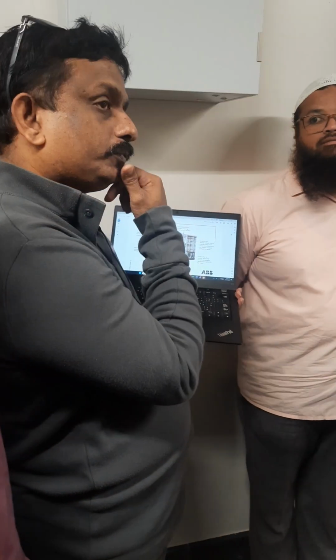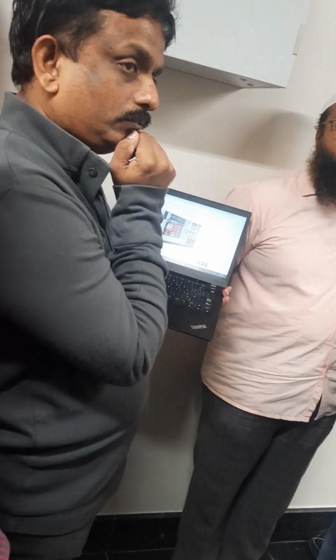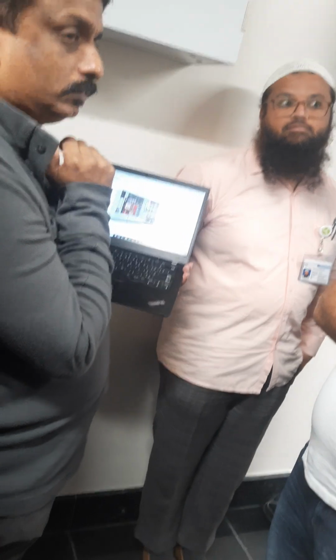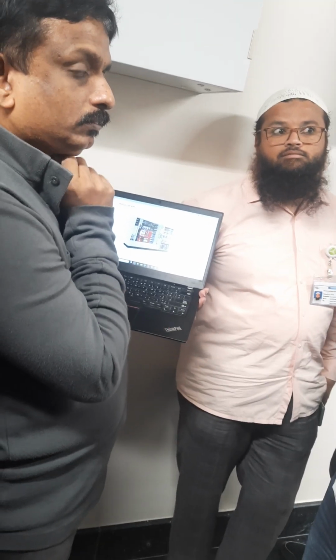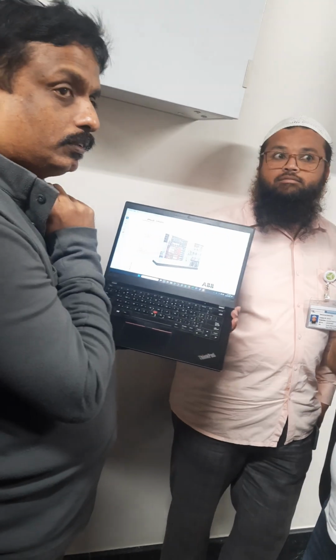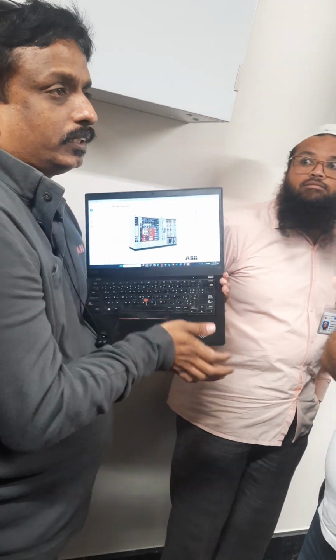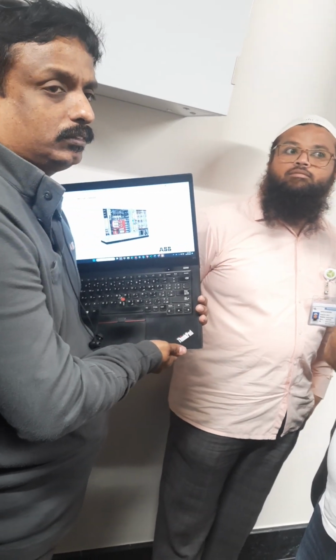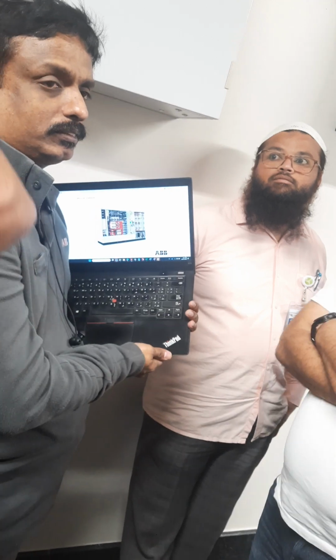So Yunus, we need to think about a backup cooling system for this room. Otherwise, due to insufficient cooling, you will get a trip. What is the maximum temperature required for this machine? At least you can keep 22. We are maintaining 22 now. It's a maximum, maximum 22.